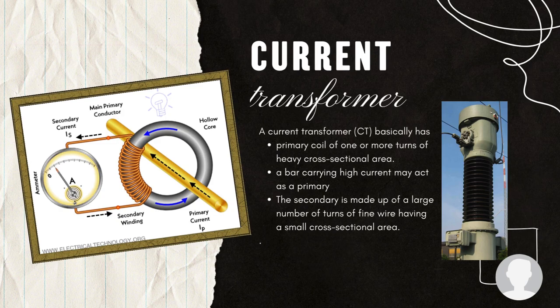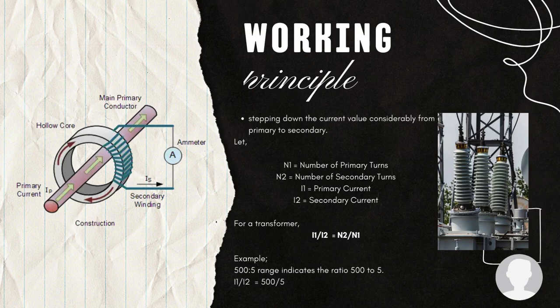A CT basically has a primary coil of one or more turns of heavy cross-sectional area. The bus bar carrying high current may act as a primary. This is connected in series with the line carrying high current. The secondary of the current transformer is made up of a large number of turns of fine wire having a small cross-sectional area, usually rated at 5 amperes. This is connected to the coil of normal range meters. These transformers are basically step-up transformers in terms of voltage, and thus the current is reduced from primary to secondary — making them step-down transformers from the current point of view.